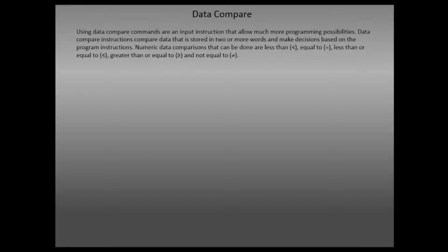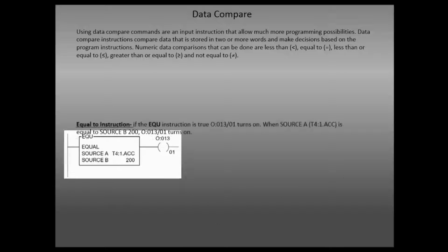Today's video is going to be a lecture on data compare instructions. We're going to be using RSLogix 500. Data compare commands are an input instruction that allow much more programming possibilities. Data compare instructions compare the data that is stored in two or more sources and make a decision based on the programming instruction. Numeric data comparisons that can be done are less than, equal to, less than or equal to, greater than or equal to, or not equal to.